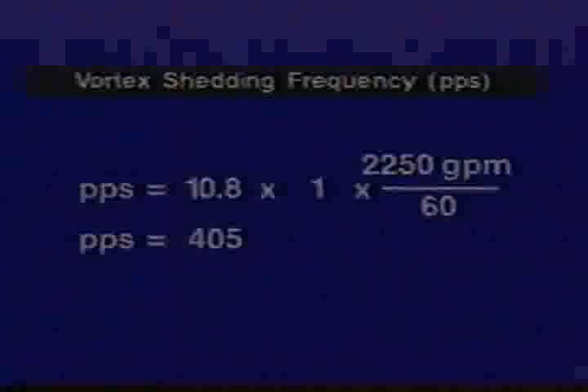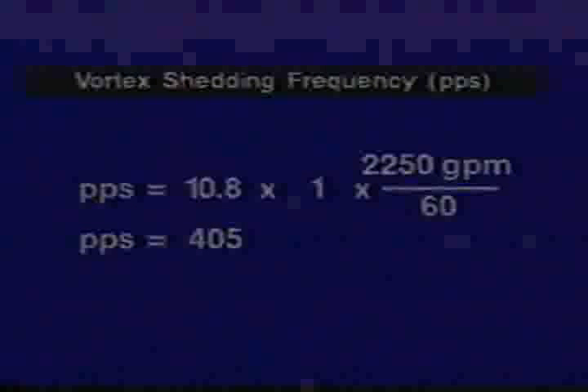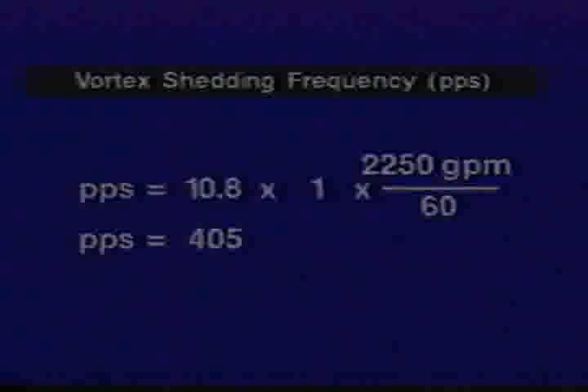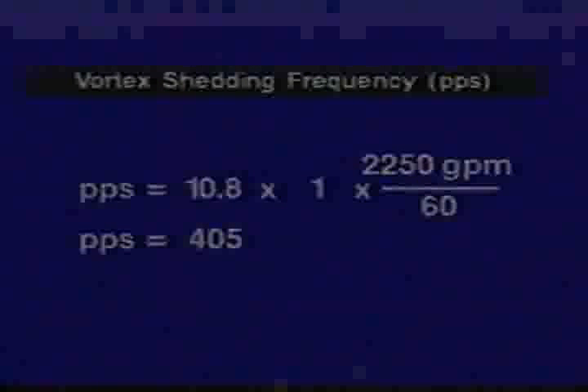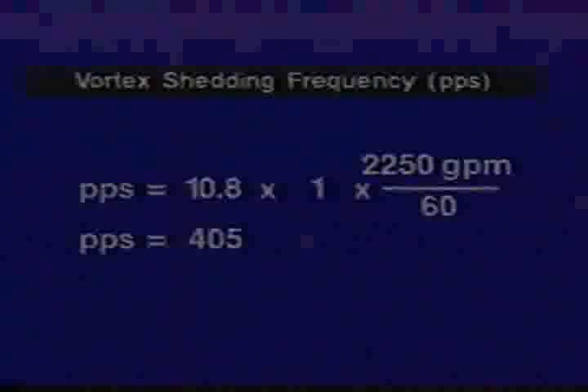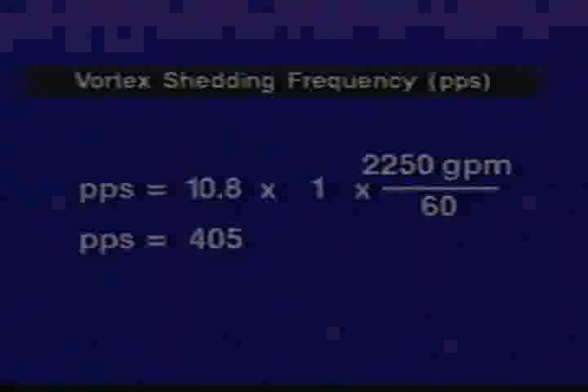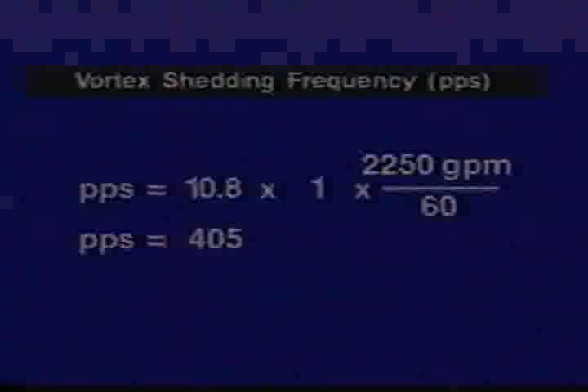Working through the calculations, we find the vortex shedding frequency, or PPS, is 405 PPS for this example. We'll use this value along with a table provided by the manufacturer to determine the calibration settings. Span jumpers are required to calibrate this transmitter. They're used to define the application range for the vortex shedding flow meter test. The manufacturer's instructions provide the appropriate settings for the coarse span jumpers.